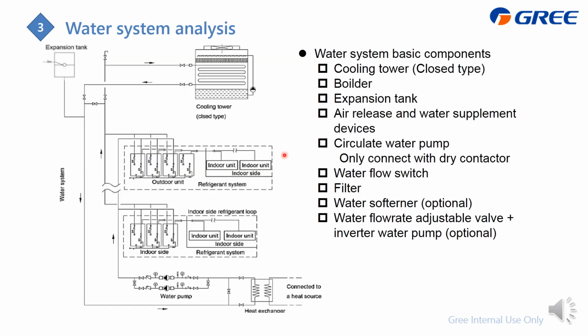And this is the water system diagram. From here you can find this is the VRF system, which is completely the same as the air cool. So in this case, we have 2. And then for the water system, they are the same as the chiller, which means we need to equip the cooling tower, the expansion tank, and also the water pump.